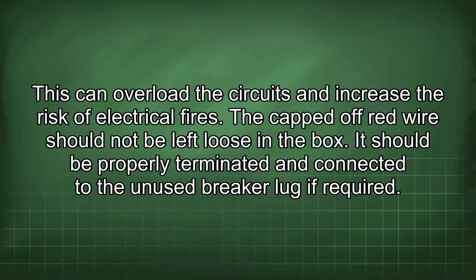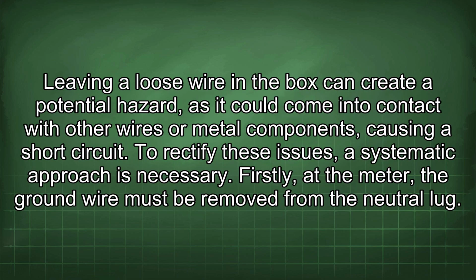The capped-off red wire should not be left loose in the box. It should be properly terminated and connected to the unused breaker lug if required. Leaving a loose wire in the box can create a potential hazard, as it could come into contact with other wires or metal components, causing a short circuit.